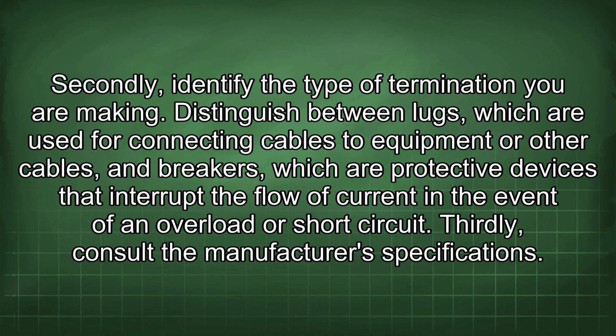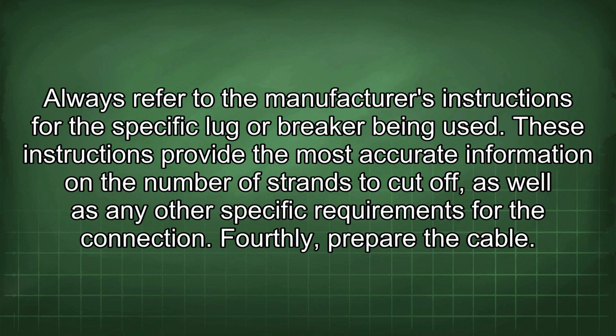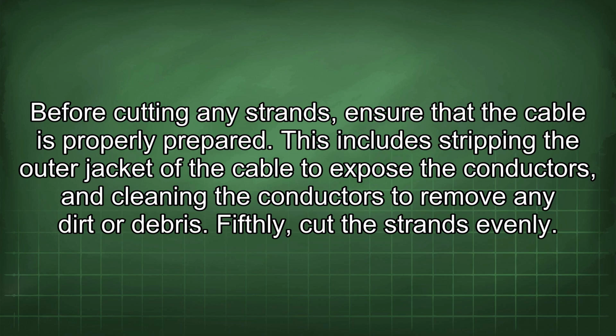Thirdly, consult the manufacturer's specifications. Always refer to the manufacturer's instructions for the specific lug or breaker being used. These instructions provide the most accurate information on the number of strands to cut off, as well as any other specific requirements for the connection. Fourthly, prepare the cable. Before cutting any strands, ensure that the cable is properly prepared. This includes stripping the outer jacket of the cable to expose the conductors and cleaning the conductors to remove any dirt or debris. Fifthly, cut the strands evenly.